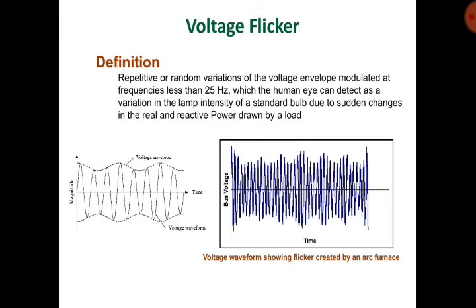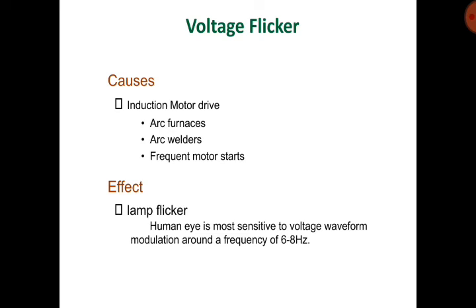Voltage flicker is the variation in lamp intensity of a standard bulb which the human eye can detect, due to sudden changes in the real and reactive power drawn by the load. Causes of voltage flicker include: induction motor drives, arc furnaces, arc welders, and frequent motor starts. The effect is lamp flicker. The human eye is most sensitive to voltage waveform modulation around a frequency of 6 to 8 Hz.